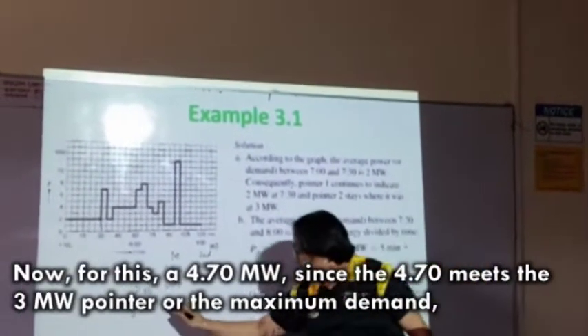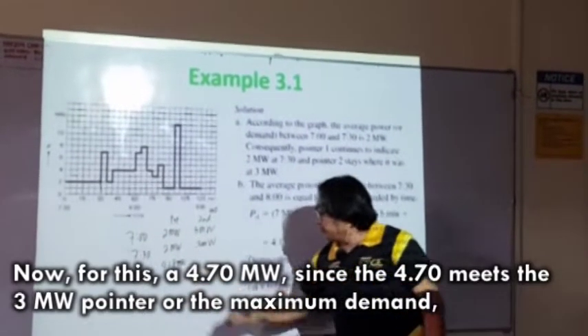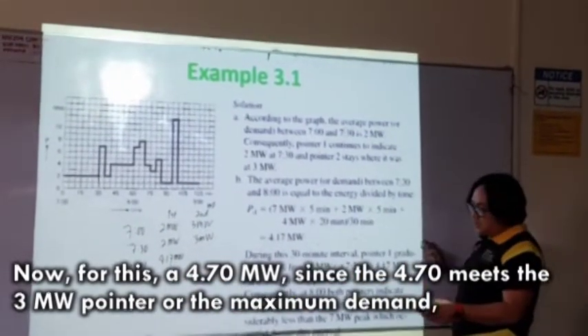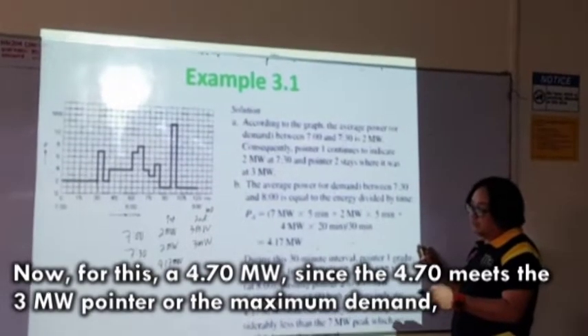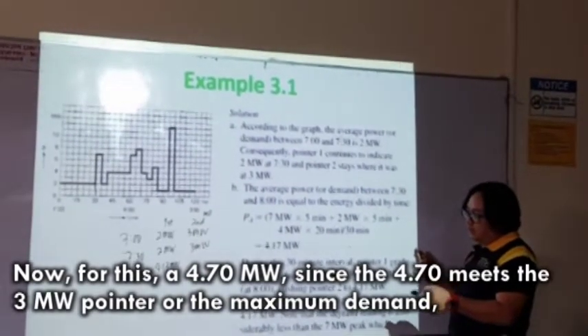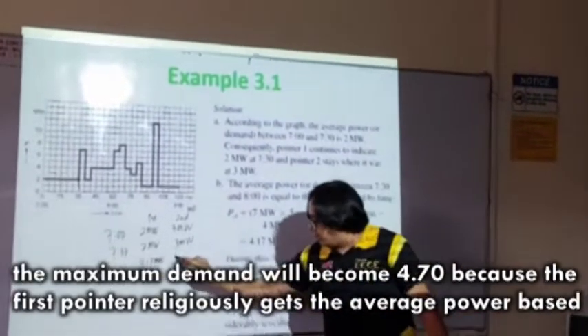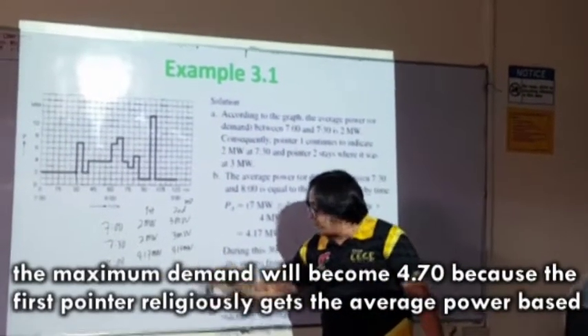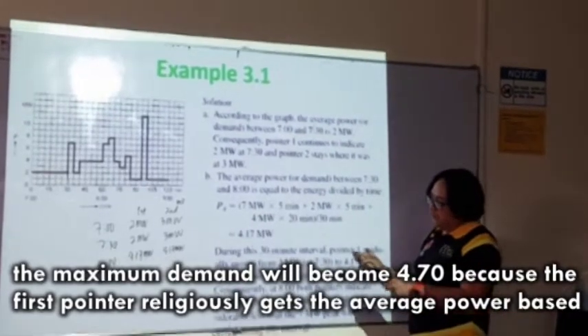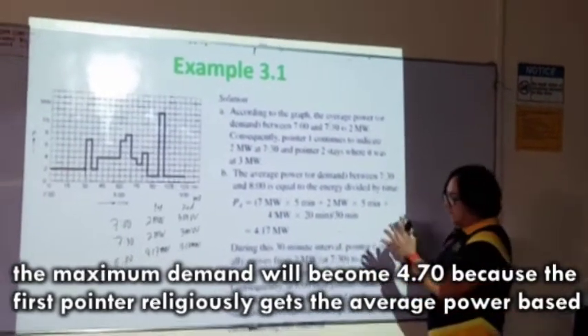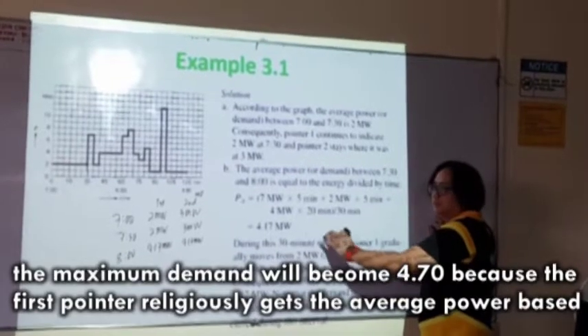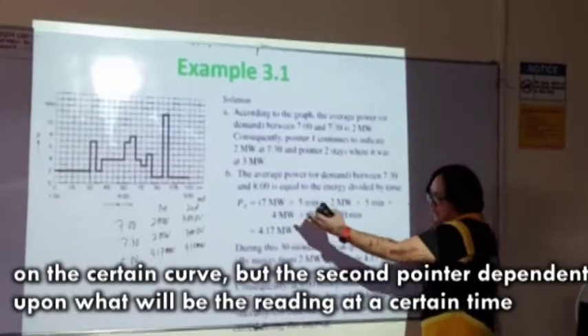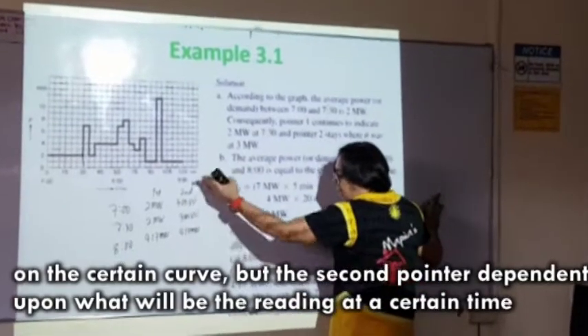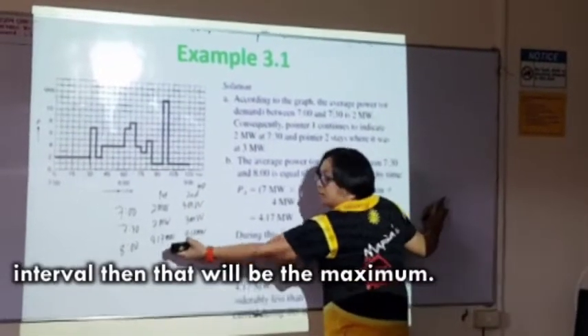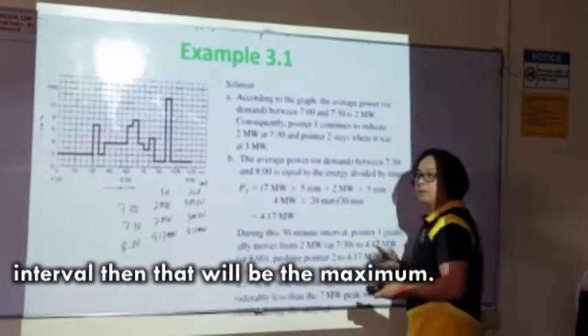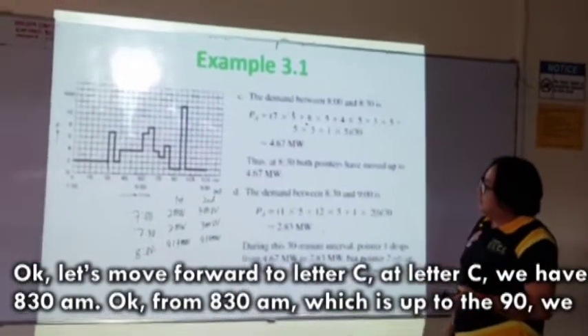Now for this, 4.17 megawatts, since the 4.17 beats the 3 megawatt pointer, or the maximum demand, the maximum demand will become 4.17 now. Because the first pointer religiously gets the average power based on a certain curve, but the second pointer will be dependent upon the reading at a certain time interval, and that will be your maximum. Let's move forward to letter C.